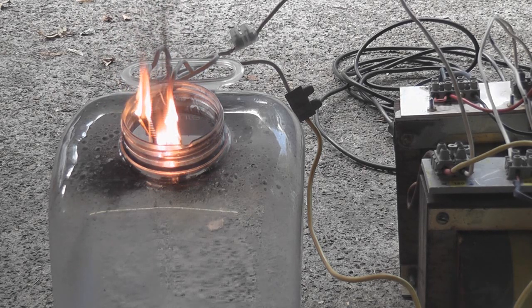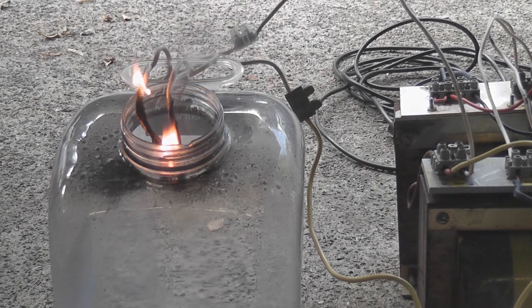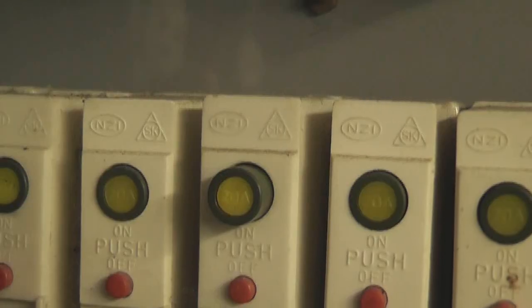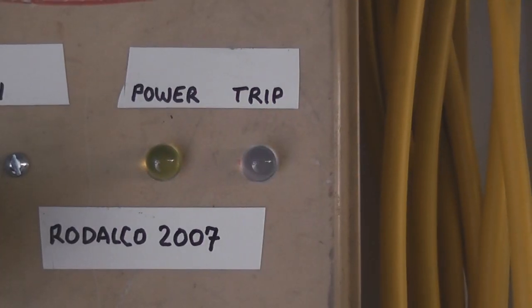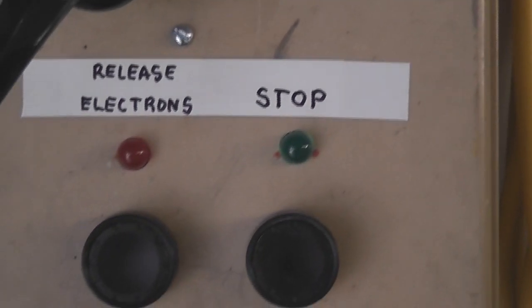Pulling fan on. Not too bad. Protection worked — the 20 amp circuit breaker popped, and the remote trip indicator shows we had to trip and de-energize the contactor as well.